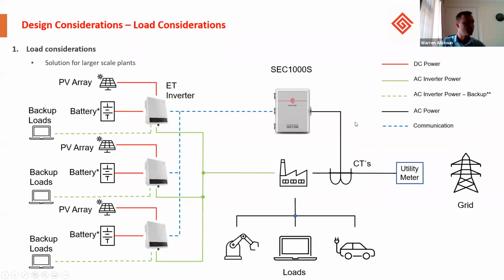For larger solutions, the GoodWe ET inverter can be paralleled up to 10 units using the SEC 1000S. This is the way the system would be configured. The backup loads cannot be paralleled, so each inverter will have its own set of backup loads, but the peak PV demand to support the small commercial system or very large residential can support all the large loads on the on-grid side.